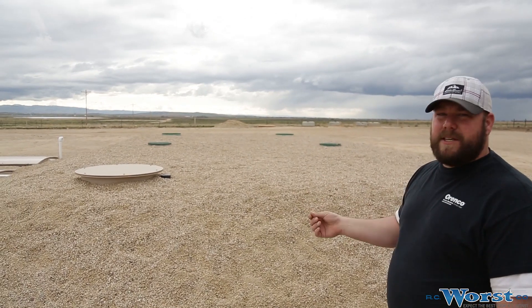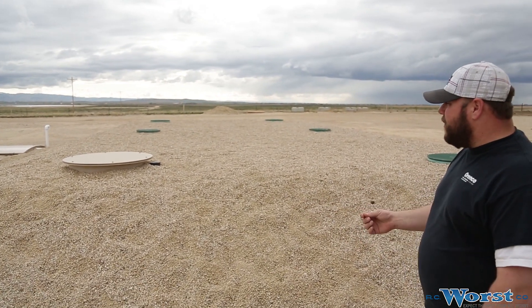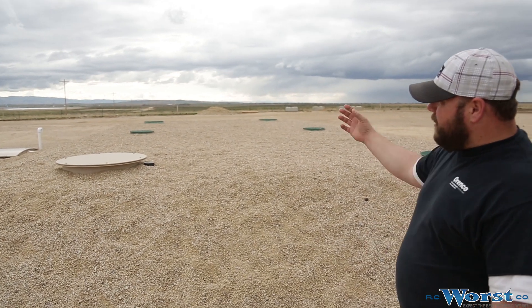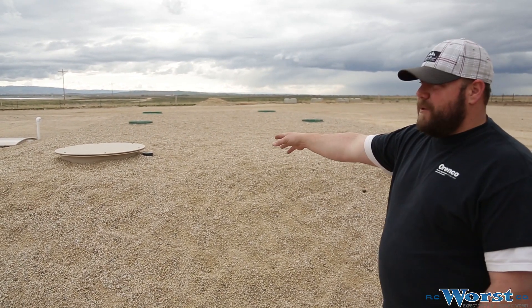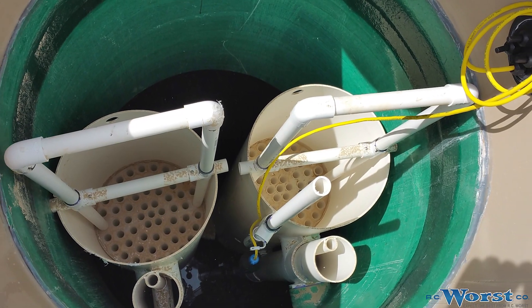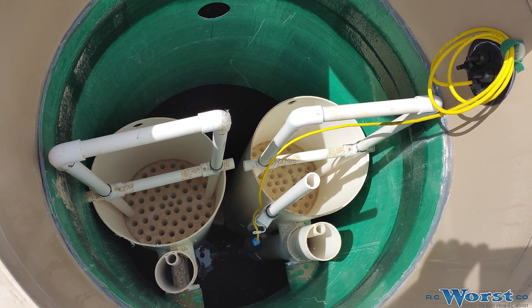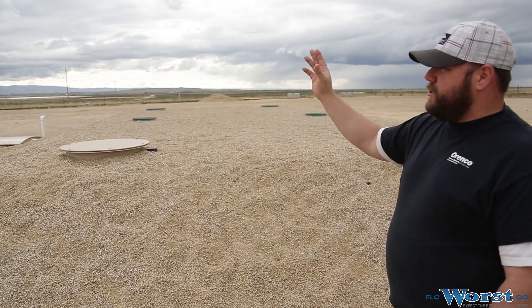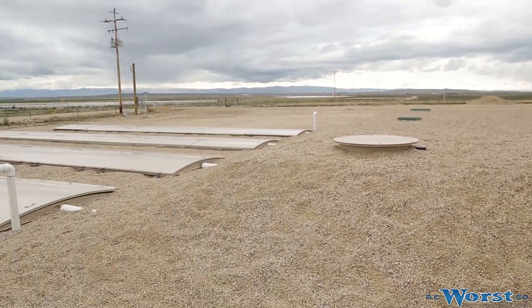We're actually returning some of our recirc blend into here to aid in the denitrification process. We blend through this tank where we hit the end, where we have a pair of 15-inch effluent filters to filter out any additional TSS and slight BOD reduction, prior to going over to the AX Max treatment system.